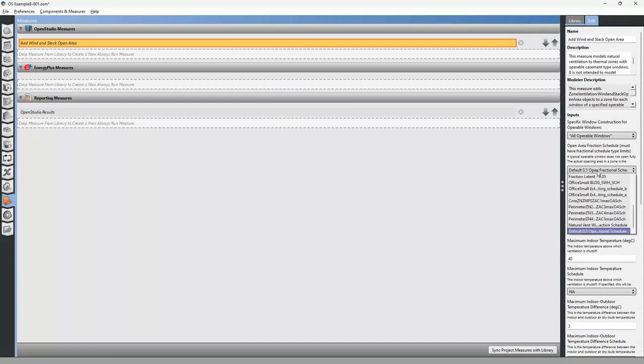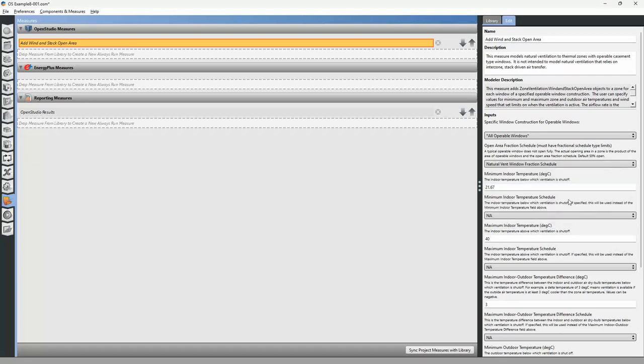Go back to the Measures tab, select the measure, and then select the custom fraction schedule we just created — 'Natural Vent Window Fraction Schedule.' There are additional parameters: minimum indoor temperature is the indoor temperature below which ventilation is shut off. Even though we have the fraction schedule, if the indoor temperature is below this value, occupants will not open the windows. You can also specify a custom temperature schedule if preferences vary throughout the day.